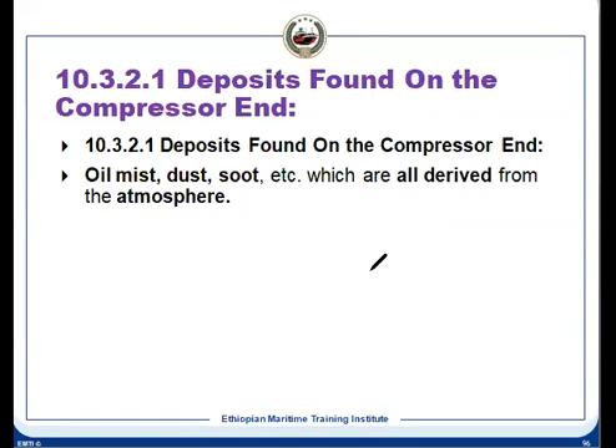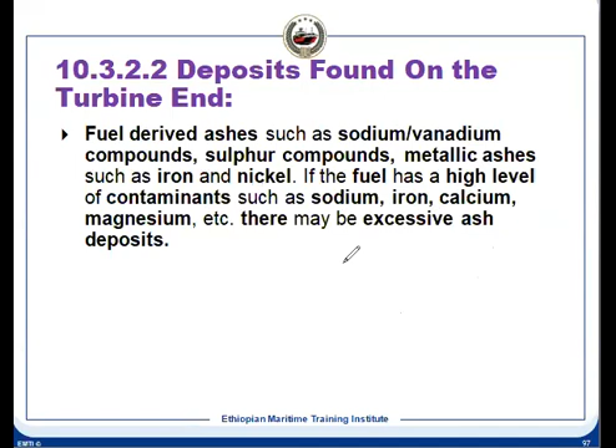And then you have the turbine side. On the turbine side, the deposit comes mainly from fuel oil impurities. So fuel oil will have sodium and vanadium, and once it is in the correct proportion, that is 3:1, it gets melted and makes a deposit. Then you have the sulfur components, metallic ashes also, iron, nickel. So fuel has all these contaminants at a high level, because we are using residual fuel, where there will be impurities. Those are not distillate fuel. So these all make a deposit on the turbine side. It will make a deposit on the nozzle ring as well as the turbine blades.